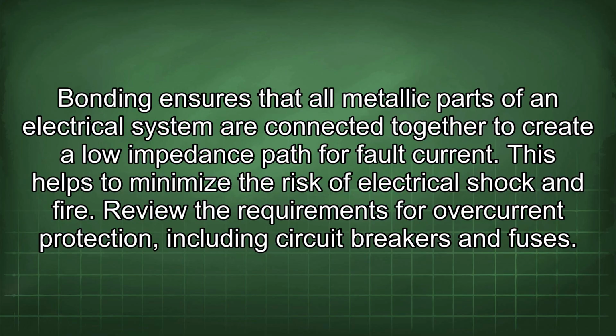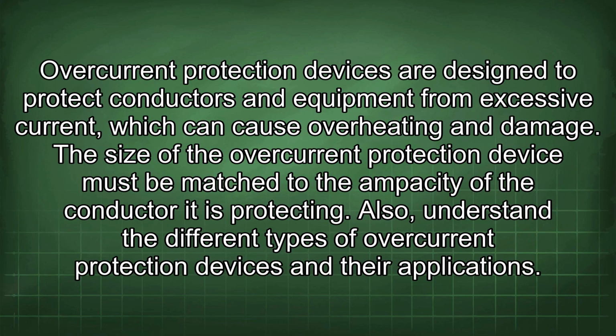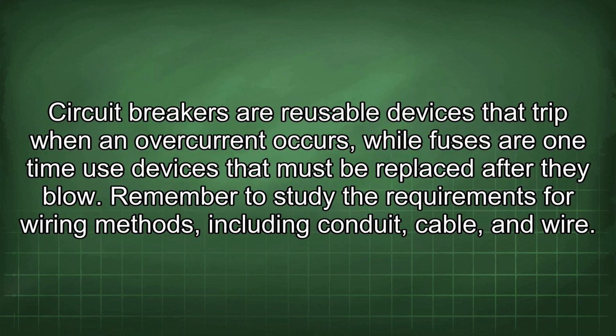Review the requirements for overcurrent protection, including circuit breakers and fuses. Overcurrent protection devices are designed to protect conductors and equipment from excessive current, which can cause overheating and damage. The size of the overcurrent protection device must be matched to the ampacity of the conductor it is protecting. Also, understand the different types of overcurrent protection devices and their applications. Circuit breakers are reusable devices that trip when an overcurrent occurs, while fuses are one-time use devices that must be replaced after they blow.